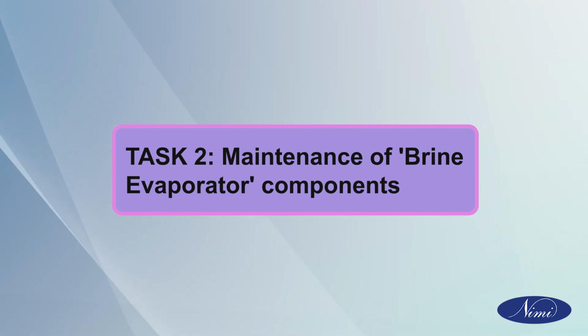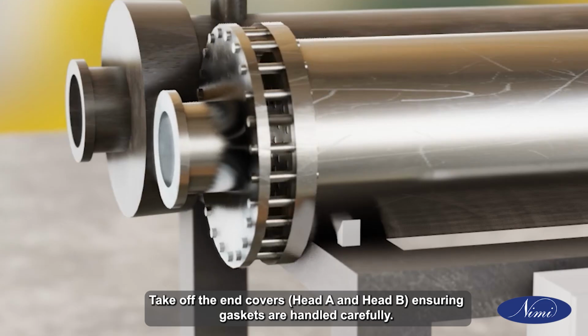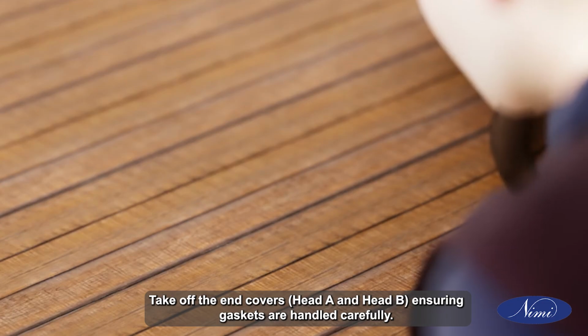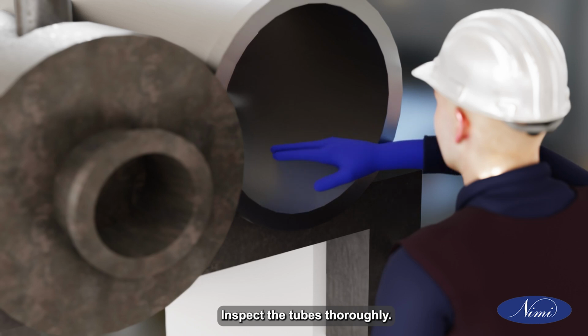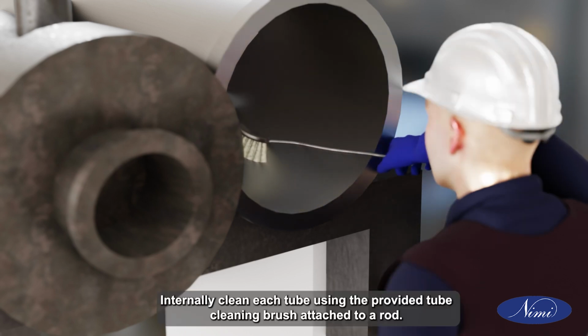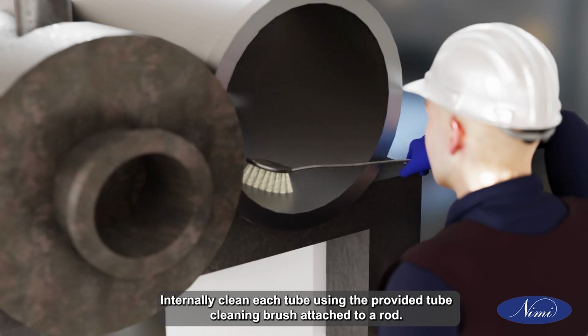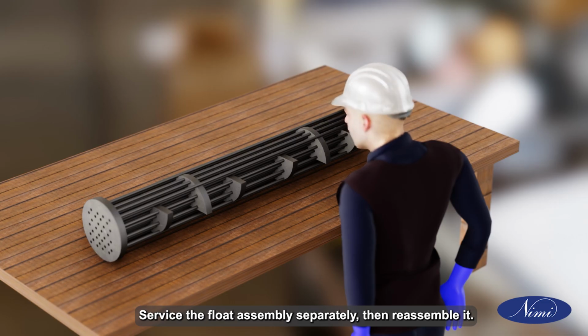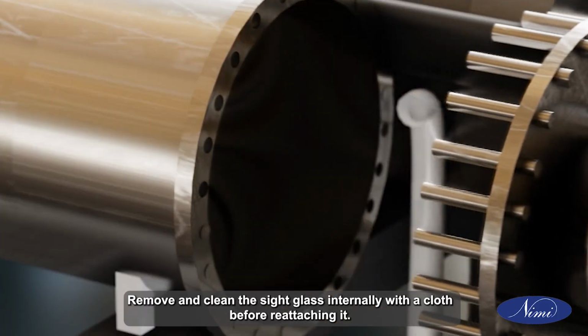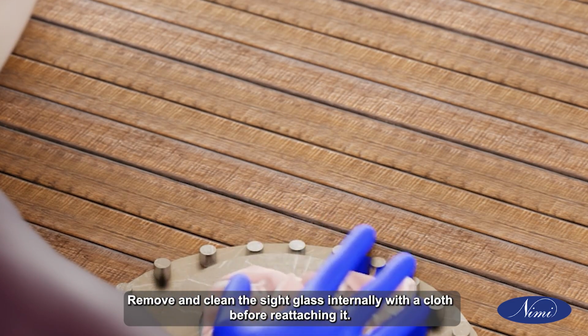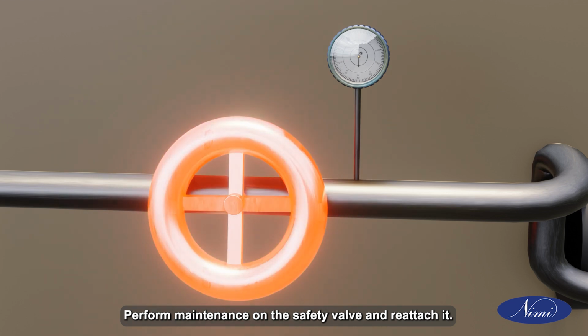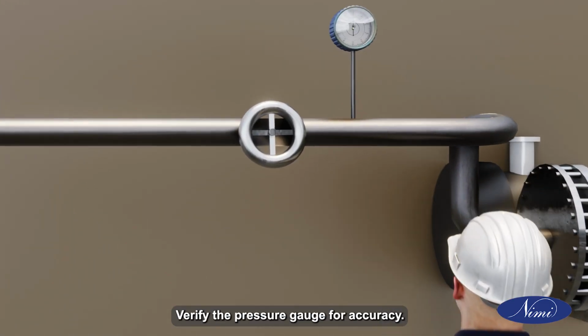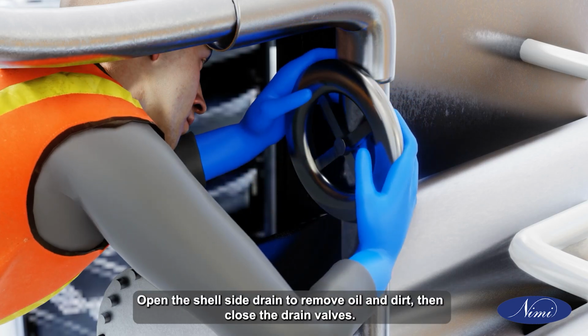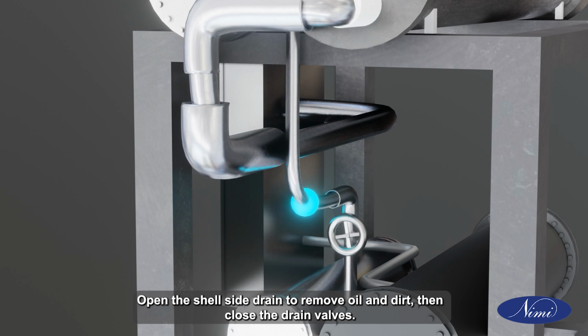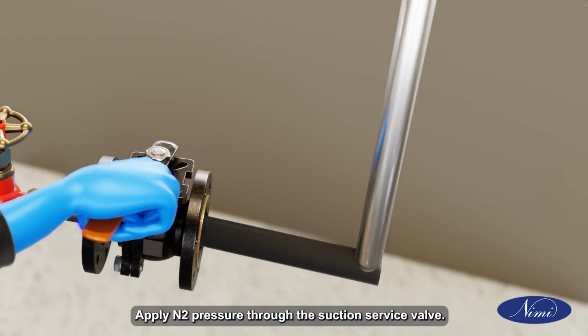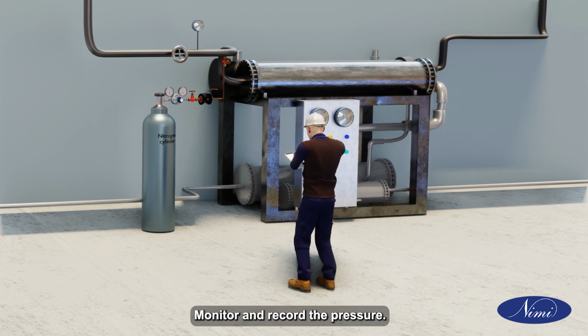Task 2. Maintenance of brine evaporator components. Take off the end covers, head A and head B, ensuring gaskets are handled carefully. Inspect the tubes thoroughly. Internally clean each tube using the provided tube cleaning brush attached to a rod. Service the float assembly separately, then reassemble it. Remove and clean the sight glass internally with a cloth before reattaching it. Perform maintenance on the safety valve and reattach it. Verify the pressure gauge for accuracy. Open the shell side drain to remove oil and dirt, then close the drain valves. Apply air pressure through the suction service valve. Monitor and record the pressure.